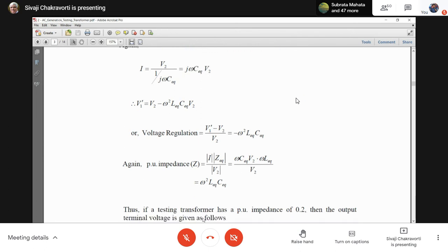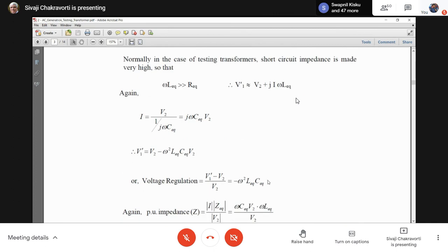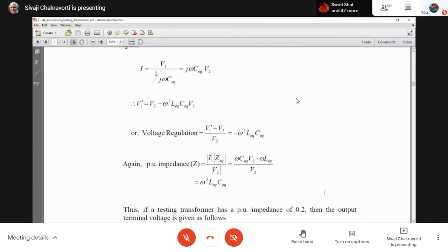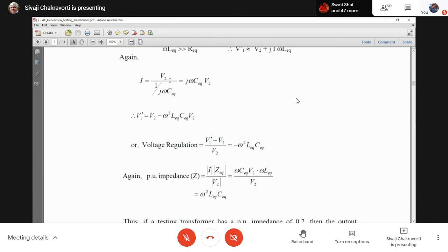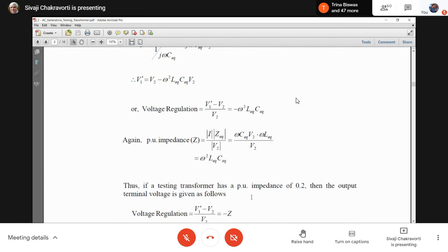Anyway, now coming to the definition of per unit impedance, I told you that it is the current into the equivalent impedance divided by the voltage. And Z equivalent, if we neglect R equivalent, is simply omega L. And current, here you can see my mouse, this is the current, so you put it here. What you find is omega square L equivalent C equivalent. Look at the voltage regulation expression. So short circuit impedance and voltage regulation have some sort of relationship. What is that? They are almost equal in magnitude.